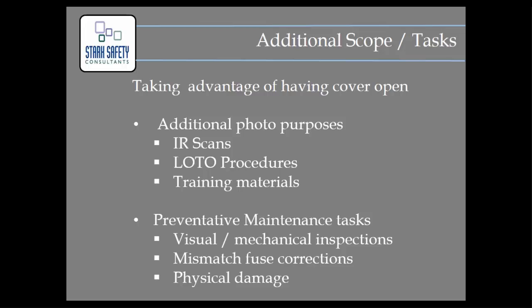Also address in the RFP how you are going to deal with mismatched fuses. How are you going to correct those when they're found? If you find different styles, different trip settings, or different brands and types, hopefully not different sizes in the same device, what's going to be the process to make those corrections, and how are you going to deal with that in your calculation?